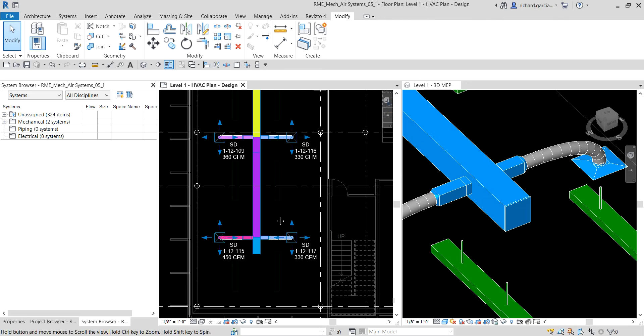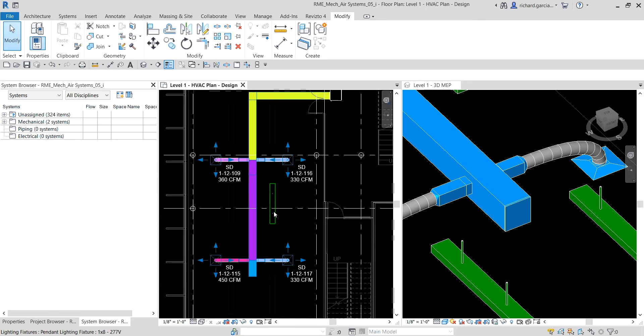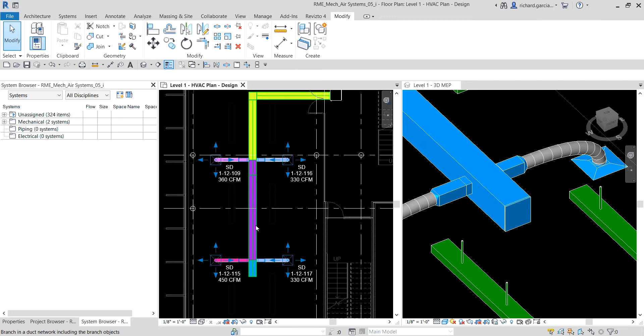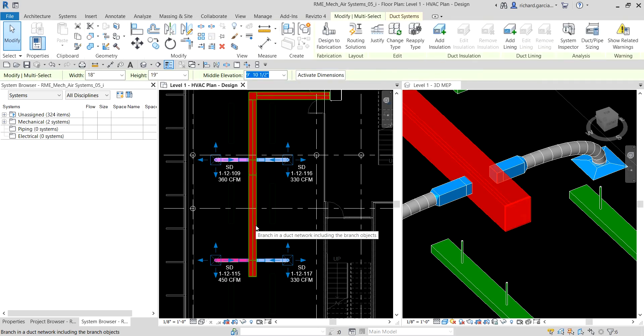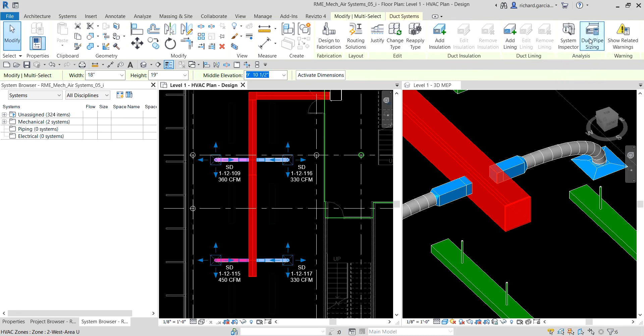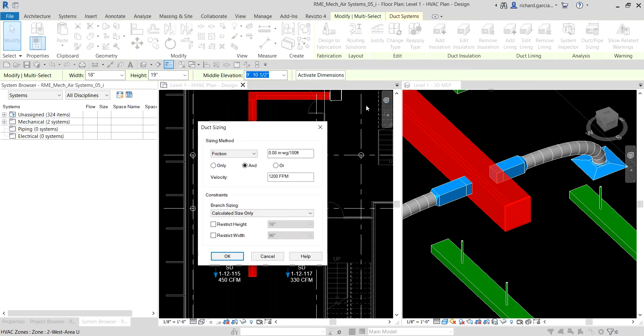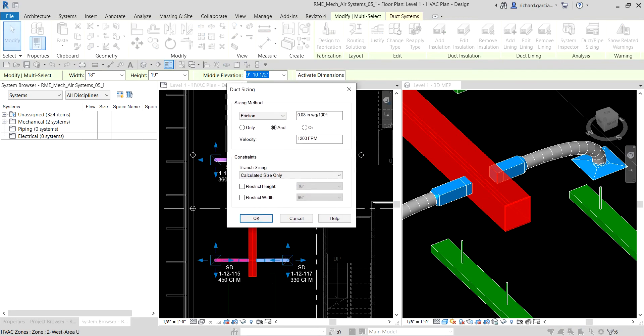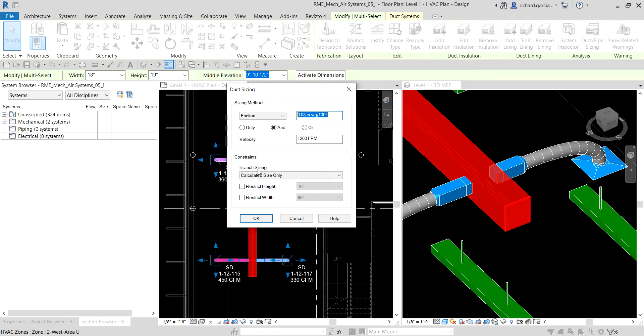Let us resize our ductwork. I'm going to hover my pointer to one of the main ducts and then press tab, and it highlights now our main duct. Click to select it, and then select duct pipe sizing. We are on the duct sizing, you can specify the sizing method that you want here. I'm going to use the default value we used last time, but this time I want to include the velocity here. Last time we only used friction only, so this time I'll use friction and velocity. I want to restrict the height, so this height constraint is used when you place duct in a restricted space such as a plenum. I want to restrict that to 16 inches. Just select okay here.